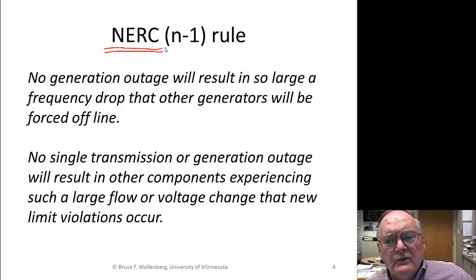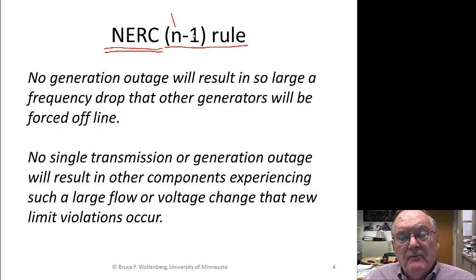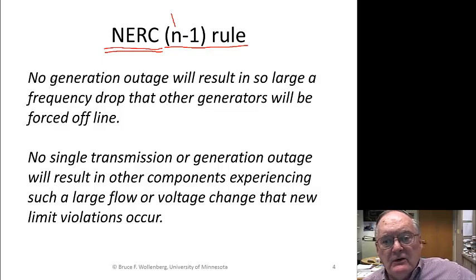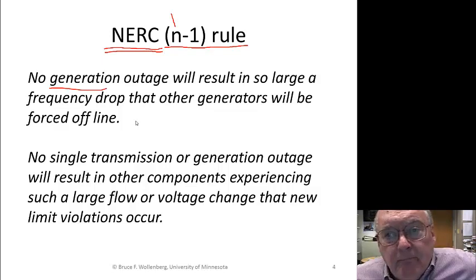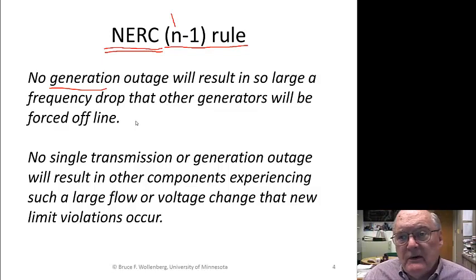They have classically had a rule called the N-1 rule, and it simply means if I have n components to start with, then n minus 1 means I have one outage. And it says that no single generator outage will result in so large a frequency drop that other generators will be forced offline. We'll learn more about this generation and frequency in the next set of lectures on generation control. But suffice it to say, when you lose a generator and you're short of generation, frequency starts to drop until all the generators can be brought up a little bit through governor action to restore the frequency. But we don't want that frequency drop to be too large.